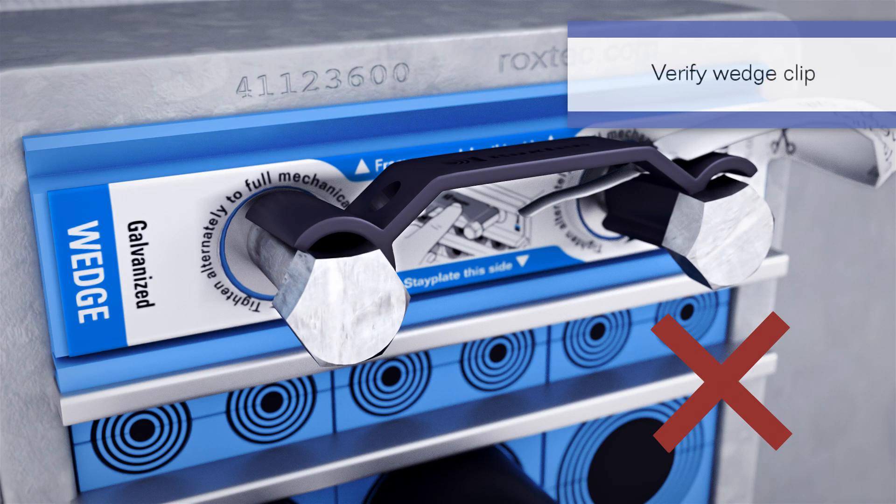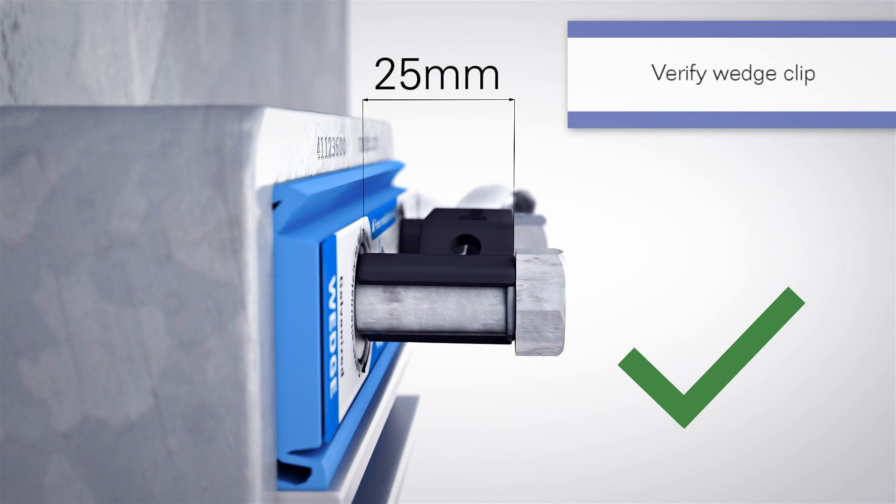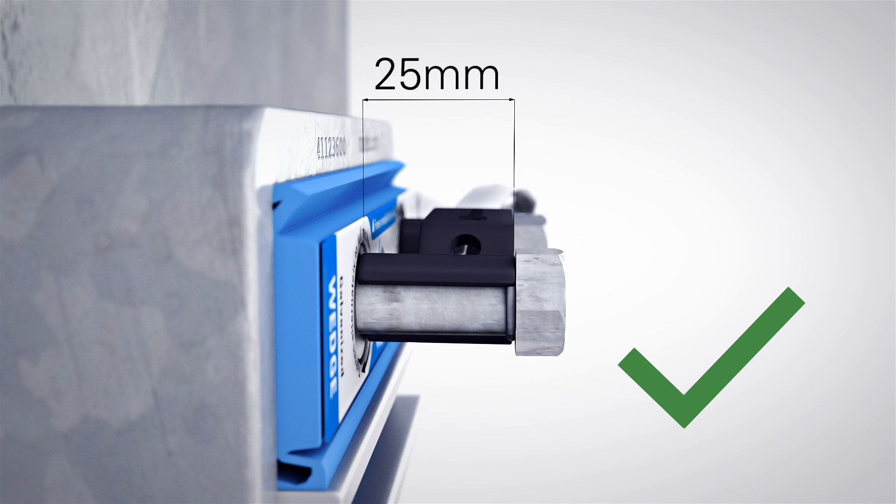Verify that the wedge clip is correctly installed and that it fits behind the bolt heads. If the clip is missing, measure the visible length of the bolt from fitting to bolt head. It must be 25 millimeters.